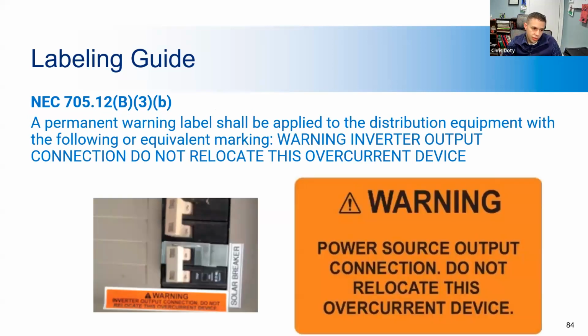Here's the power source output connection label, saying that you do not want to relocate this breaker. This is an example of, like, in the 120% rule, you want to have that backfeed breaker on the opposite side of the panel compared to the main breaker. And that's to avoid overloading the bus bar with current.